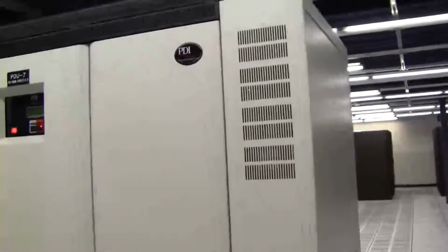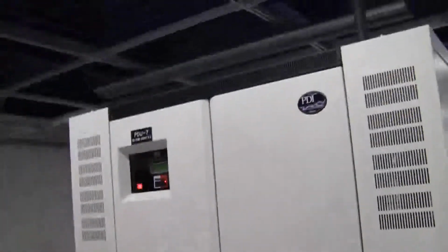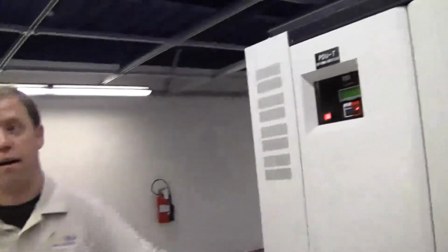This is like electrical source coming from the outside. Is this battery backup, or is it just electrical source coming from the outside? The electrical source from the outside first comes in and it goes to an automatic transfer switch. If utility power goes down from Seattle City Light for some reason, the automatic transfer switch goes, okay, I've seen the loss of power here, it switches over to generator. These are behind a UPS. So basically it goes utility power, automatic transfer switch, UPS, which has a power rectifier in it, which actually cleans the power, and then PDU, customer cabinet.